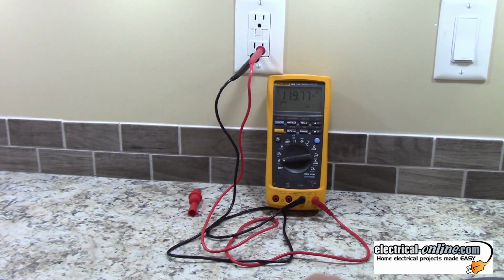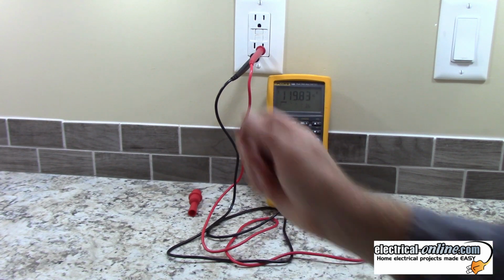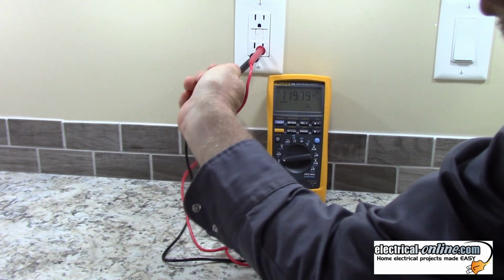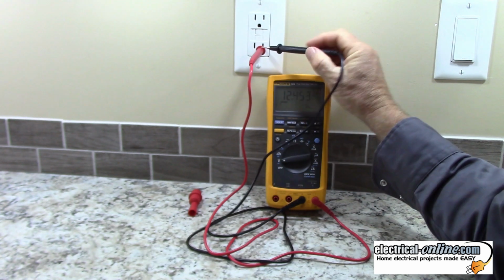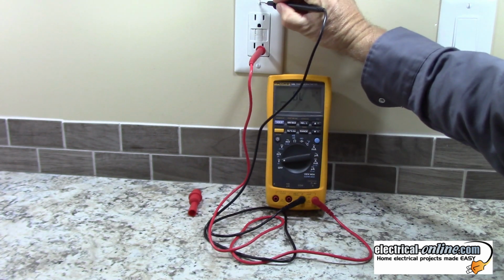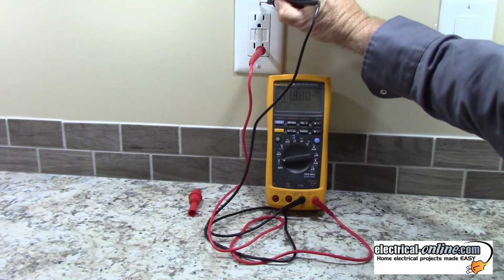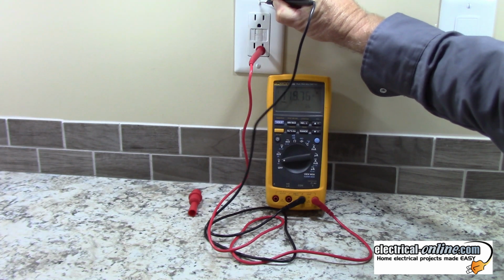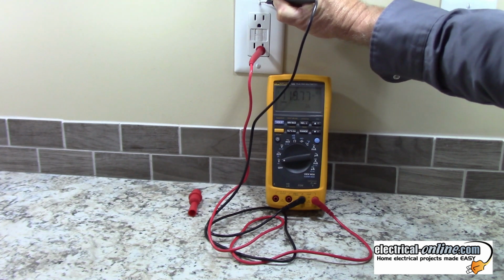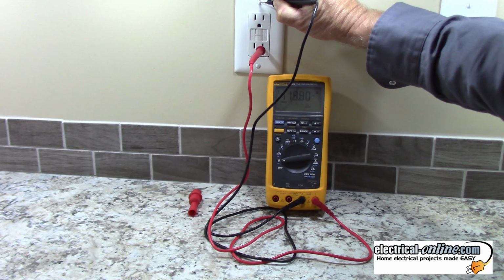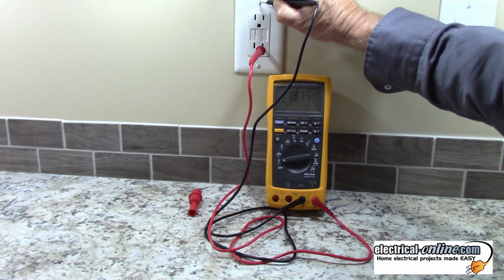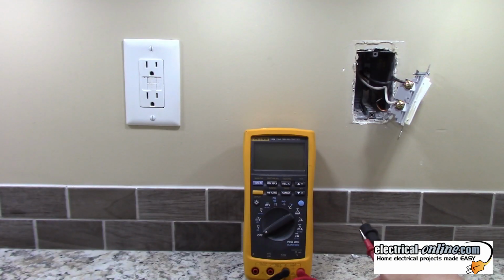And now you can also check the plate screws and see if you've got a ground on those plate screws. Leave the hot probe in, and you kind of got to dig in on that plate screw because it's painted, so you got to make sure you get a good contact there. And again, you got 119 volts from hot to ground. So I've shown you testing for power in a receptacle, and now of course you can't do that with a switch without opening it up.